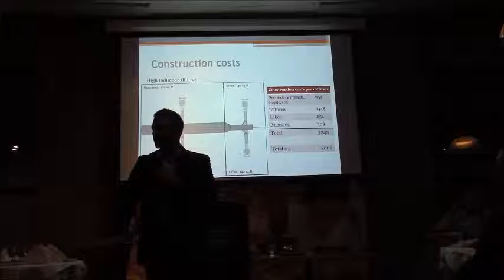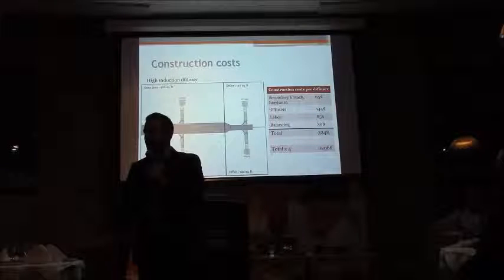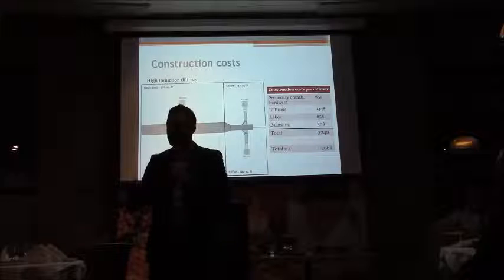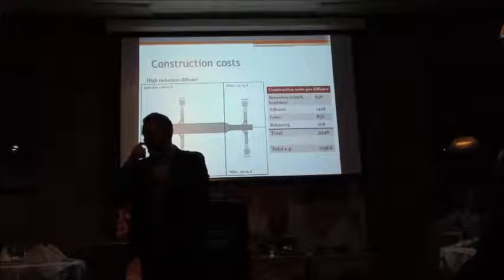So you're talking about the roof diffusers. The same type of diffusers are also used for the floor diffusing systems. So what's the trend right now for using diffusers from the floor instead of from the roof? I know that these high induction manufacturers have a model for floor diffusers, but I haven't seen many applications for floor diffusers, so it's still very limited in the market. The problem with floor diffusers is that if you have a diffuser here and then you put a table over it, or you put a plant over it... So the layout is one issue. I think that's one of the reasons I don't see a lot of floor diffusers.